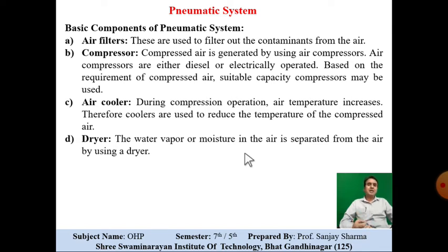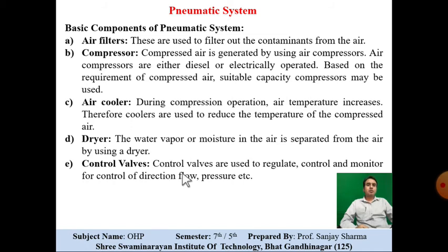If moisturized air is used, it will be responsible for the corrosion of the actuators, the direction control valves, or the spindle of the direction control valve. So it will reduce the life of the pneumatic system components. So it is very mandatory to separate the moisture from the pressurized air.